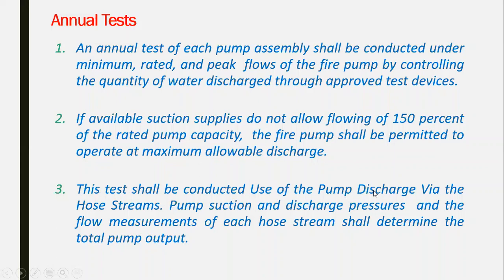Within this test, we use the pump discharge by the hose stream. Do you remember when we talked about testing the standpipe? How many connectors do we have to take for the standpipe of 1000 GPM? Do you remember? Four outlets, 4 inch each. So using the hose for discharging, because we are going to discharge the pump at full capacity, and the pump is operating at full capacity. So where do I take all of this water from? Taking from the hose streams, suction and discharge pressure, and the flow measured by the pressure gauge and the flow meters, measuring at each hose stream to determine the total pump output.